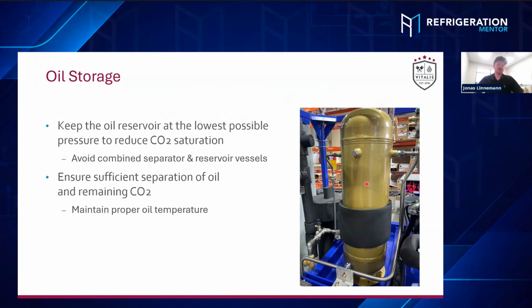Especially in smaller systems, sometimes you will see these combined oil separator, oil reservoir vessels. They might be very handy for installations, but you will always store the oil inside the discharge CO2. So we have the highest possible CO2 saturation inside the oil. And as soon as you refill that high pressured oil into the crankcase, especially low temp crankcases, it starts to expand the CO2, and you basically just produce foam, which is not very nice for the compressors, let's say.